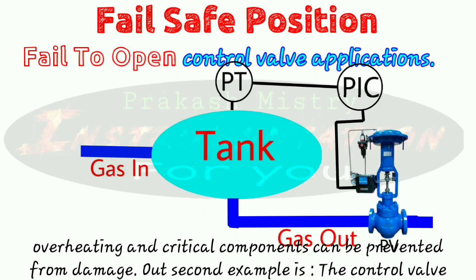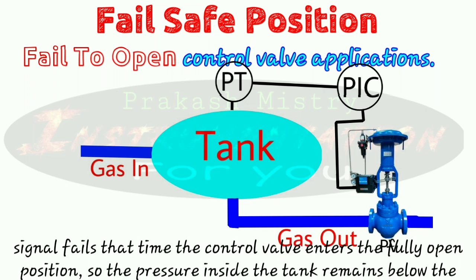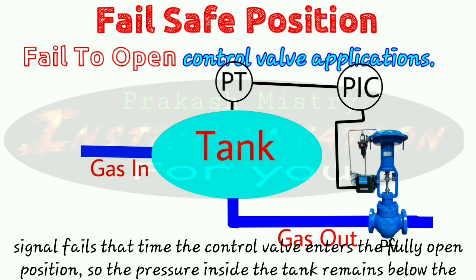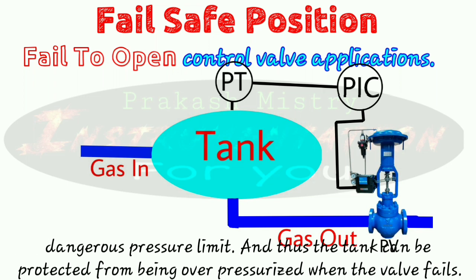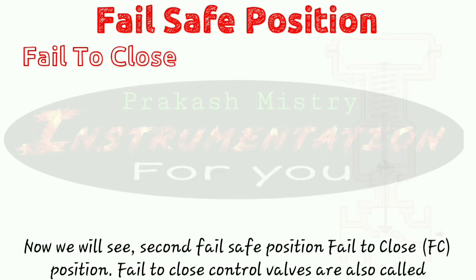A second example is the control valve which is regulating the pressure of a tank — it should be fail to open. So that whenever the power signal or control signal fails, the control valve enters the fully open position, and the pressure inside the tank remains below the dangerous pressure limit. Thus, the tank can be protected from being over-pressurized when the valve fails.